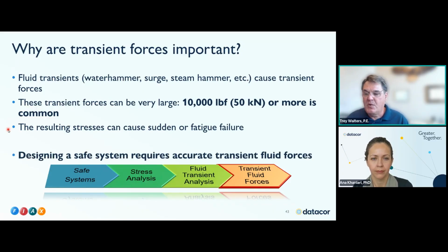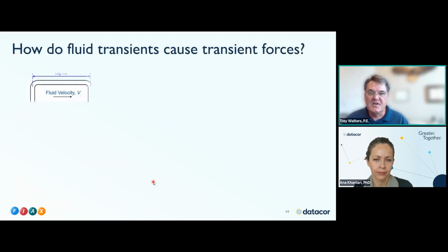Designing a safe system requires accurate transient fluid forces. What that means is, to have safe systems, you have to have stress analysis. You need a fluid transient analysis, which Impulse can do for liquids and xStream for gases and steam. And then you need those transient fluid forces to feed back into the dynamic stress analysis to make sure the pipe supports are properly designed.